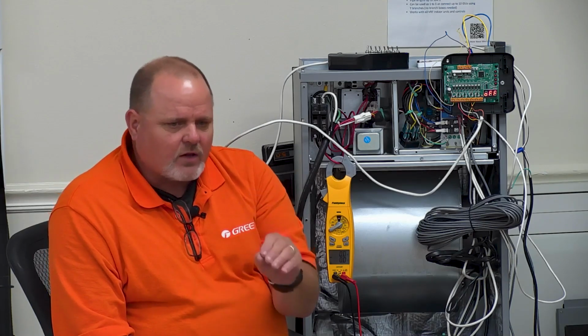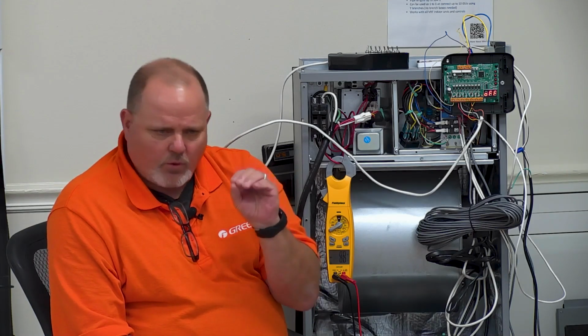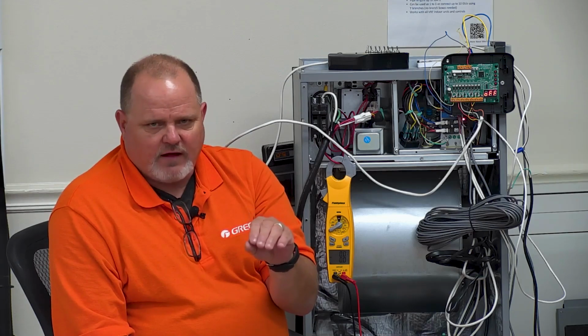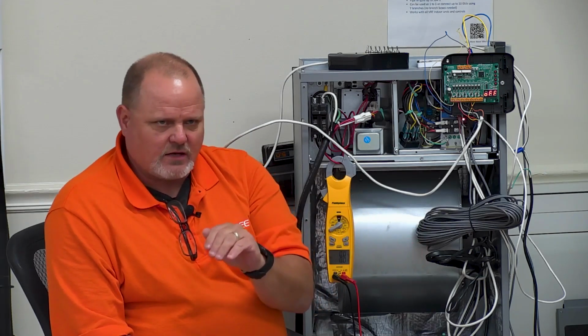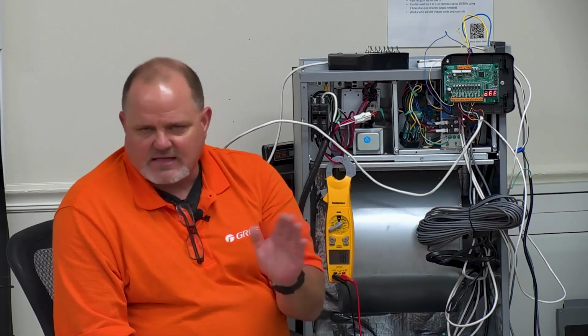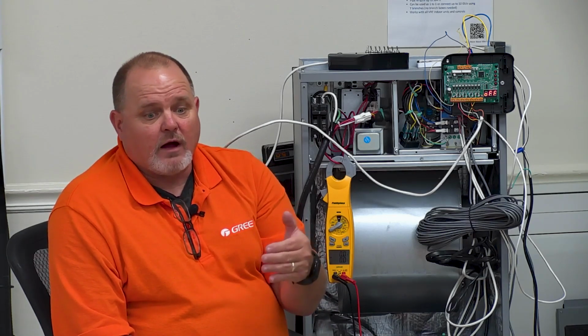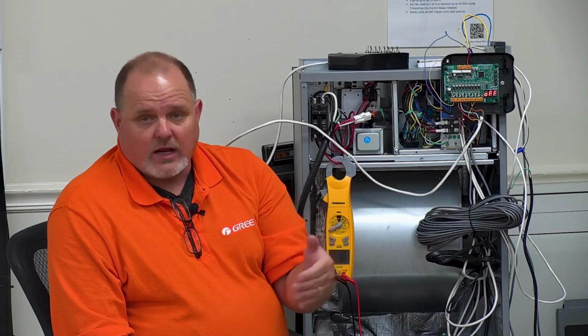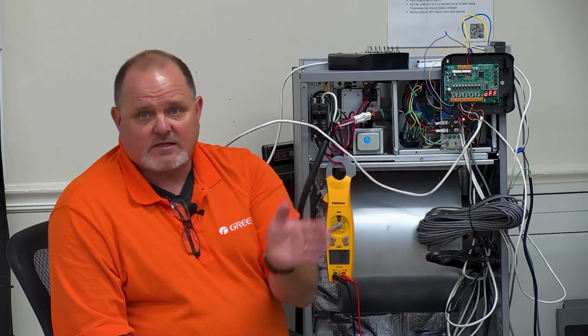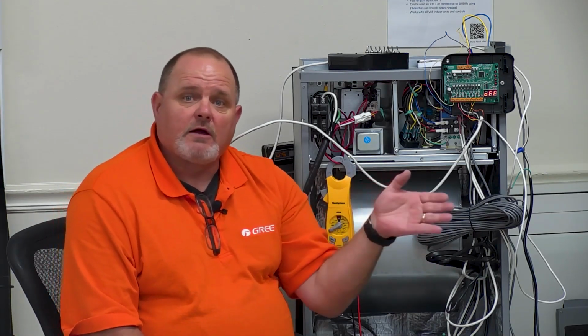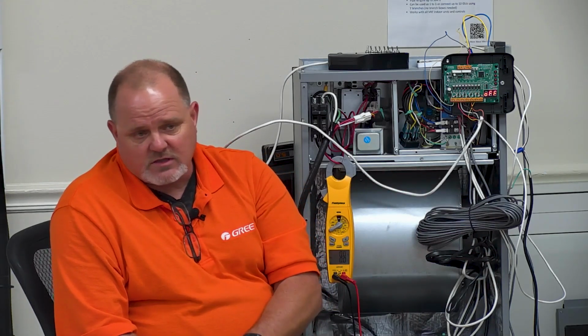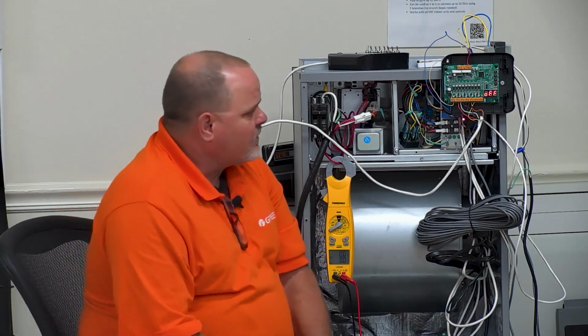It's not going to be a direct correlation into if my total static is 0.5, I need setting 5. If my total static is 0.9, I need setting 9. That's not really what it means. What it really means is that you're just giving the blower profile the ability to run at a higher RPM if you set the static curve higher, a lower RPM if you set the static curve lower. So that's really what it's about. But it's not going to fix bad ductwork for you guys. So you've got to have good ductwork so the airflow can move, okay? Got to use good filters too.